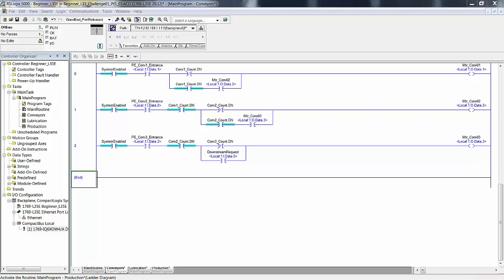We're back now with our three conveyor motor rungs. In the manual we have the logical statement of what you see in front of you. Conveyor one runs if this bit is set on in memory - assuming the system is enabled - if photo eye one is blocked at the entrance of conveyor one, we want the conveyor to run unless the conveyor is full. Conveyor one count has to be not done; if it's full, this will be false and the motor won't run.